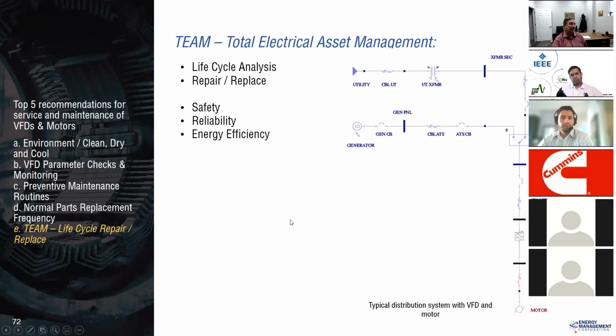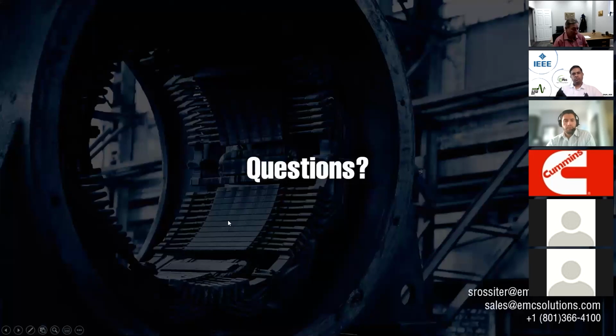For example, capacitors are one of the, I skipped over normal part replacement. Fans are the main mechanical device that you need to plan on replacing every so often. But manufacturers vary quite differently. Some would say replace capacitors after 10 years. We've got many drives operating into 20 years with no capacitor replacement. Allen Bradley, in their literature, would say you should replace the capacitors every 3 years. I found this life cycle repair replace program that we've done for our customers to be very valuable in really tuning in on the right time frame and frequency for the repair and replacement.